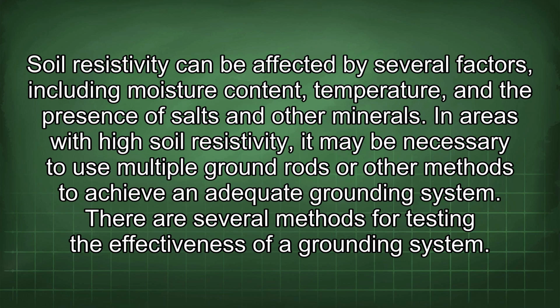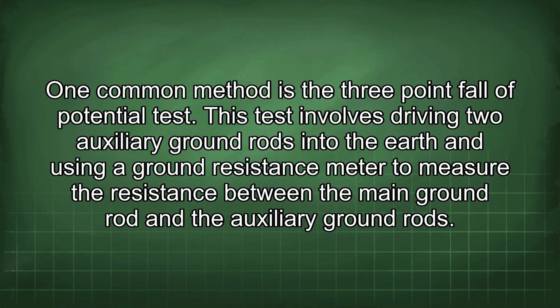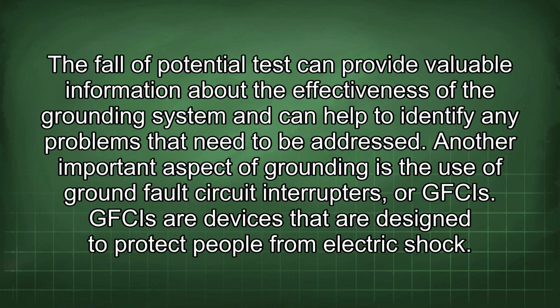an adequate grounding system. There are several methods for testing the effectiveness of a grounding system. One common method is the 3-point fall of potential test. This test involves driving two auxiliary ground rods into the earth and using a ground resistance meter to measure the resistance between the main ground rod and the auxiliary ground rods. The fall of potential test can provide valuable information about the effectiveness of the grounding system and can help to identify any problems that need to be addressed.